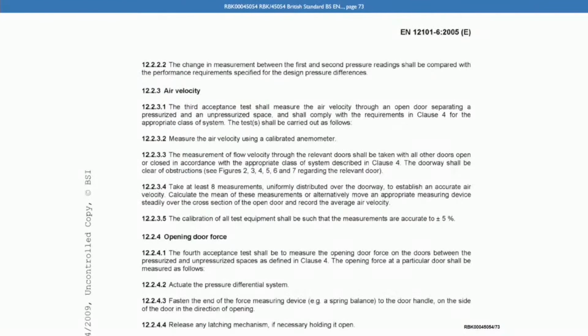That was my next question. So this standard requires you to do it within 15 minutes of the first test. You're saying that you didn't do that. You did them on separate occasions. Is that correct? We did them on more than one occasion, but yes. Now, can we agree that it requires measuring the net pressure differential across each door between a pressurised and an unpressurised space to the relevant accommodation on all floor levels with the pressure differential system running?